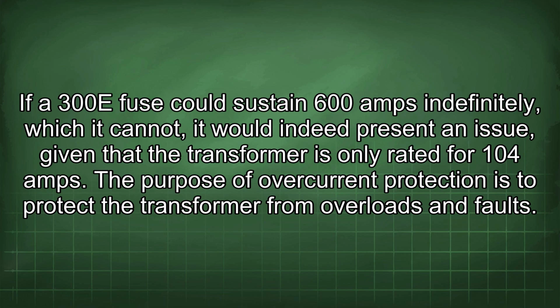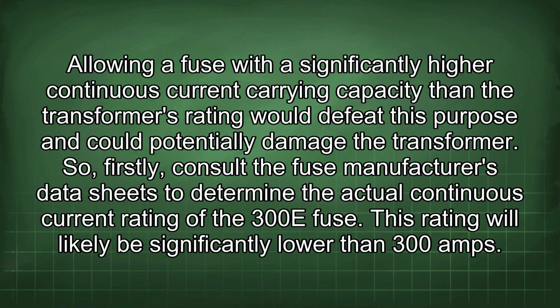The purpose of overcurrent protection is to protect the transformer from overloads and faults. Allowing a fuse with a significantly higher continuous current carrying capacity than the transformer's rating would defeat this purpose and could potentially damage the transformer. So, firstly, consult the fuse manufacturer's data sheets to determine the actual continuous current rating of the 300E fuse. This rating will likely be significantly lower than 300 amps.